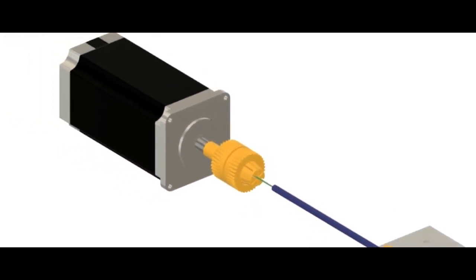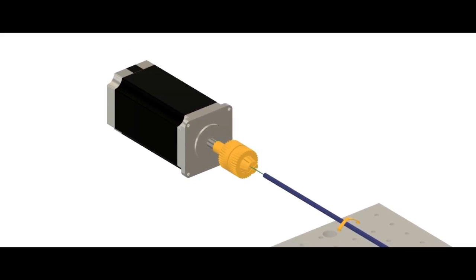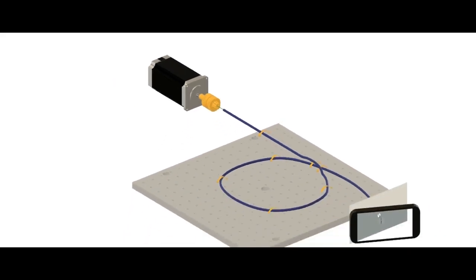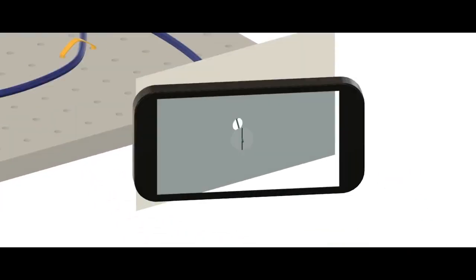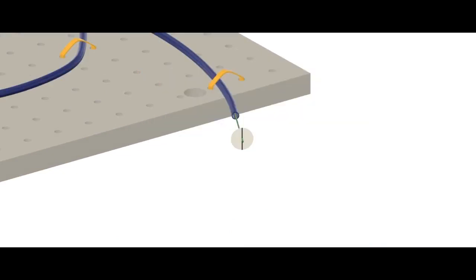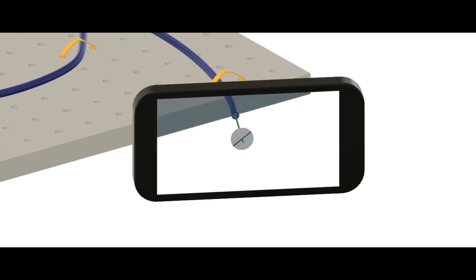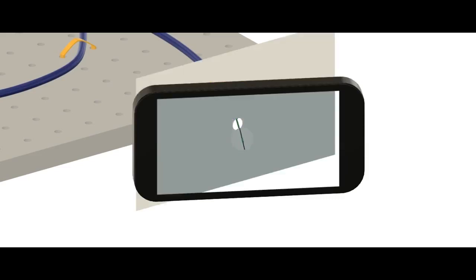As to the torqueability test itself, the stepper motor rotates the guidewire catheter's proximal end 360 degrees in 2 seconds, simulating the approximate speed of a person rotating their hand. The angular rotation of the distal end of the guidewire catheter is measured by the optical measurement system, where an optical flag is inserted onto the distal end of a guidewire catheter. During the torqueability test, a smartphone's camera is used to record video of the optical flag rotating in response to the stepper motor rotation. A white background is used to aid in video analysis.